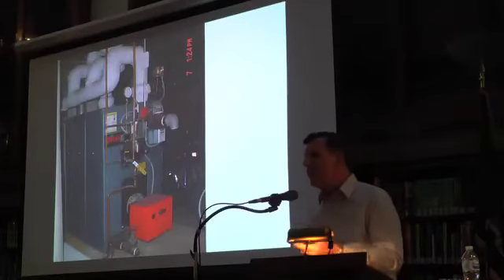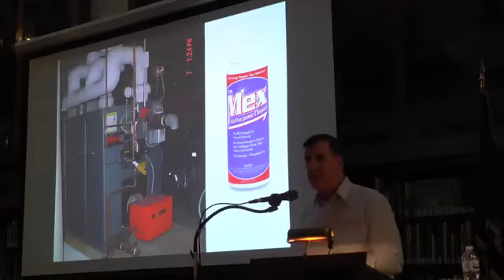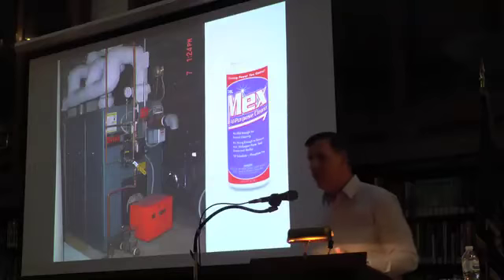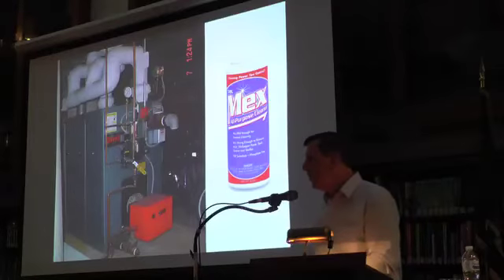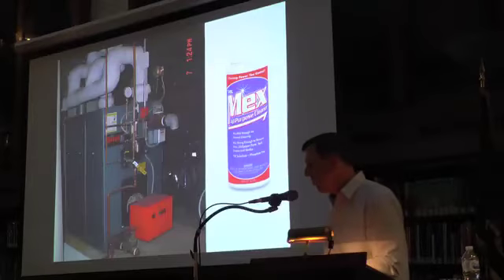So nowadays with the boilers, if you're cleaning, there are chemicals for this and all that, but a real good product to use that's been used for many years is called Mex, and you can pick this up in any hardware store. And Mex is just a really, really strong cleaner. And it's soap, so it's not going to hurt anything in a boiler. It won't hurt rubber gaskets or anything like that. It's not like adding petroleum products to something that has rubber in it. And with the Mex, you just use 1 pound per 50 gallons of water in the boiler. You don't need much of it. You put it in there, and heat it up in a bucket, throw it into the boiler, and just let it steam. I'll show you how to get rid of it later by using valves on the boiler. But that's what we do.